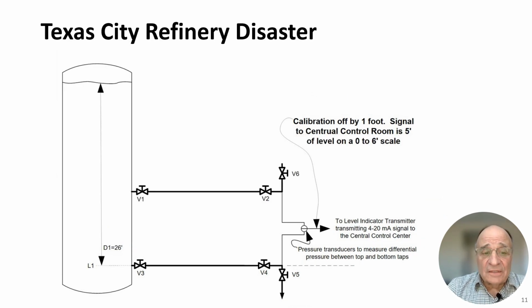Remember in the earlier slide when the level was at 6 foot and showed at 5 foot here? Well, if that same vessel now had 26 foot of head, it would still be reading 5 foot level here. The operator would be thinking that the level's at 5 foot, and this becomes 26 foot, 27 foot, overflows the vessel, and you have a catastrophe. That is what happened at the Texas City refinery.